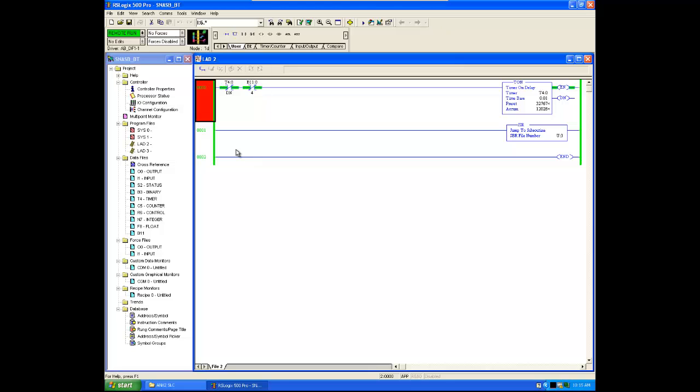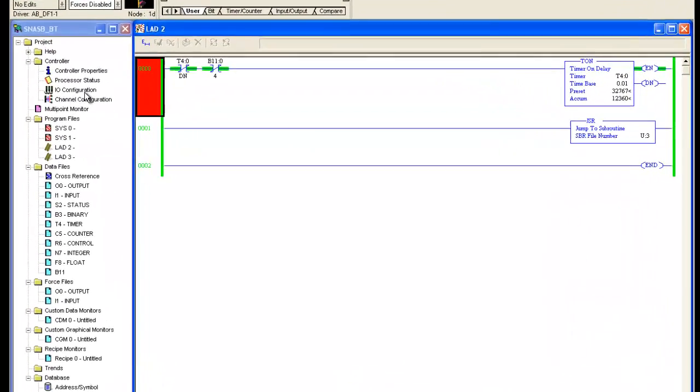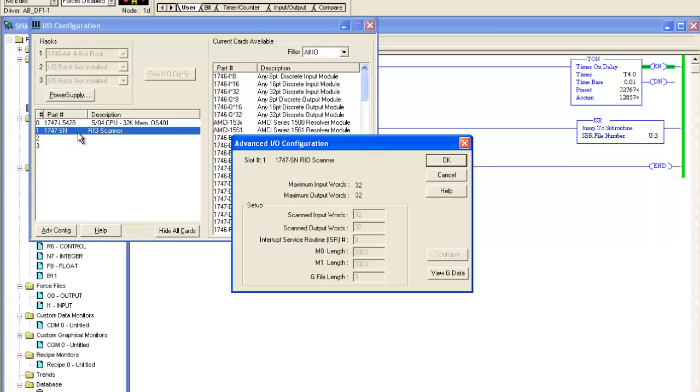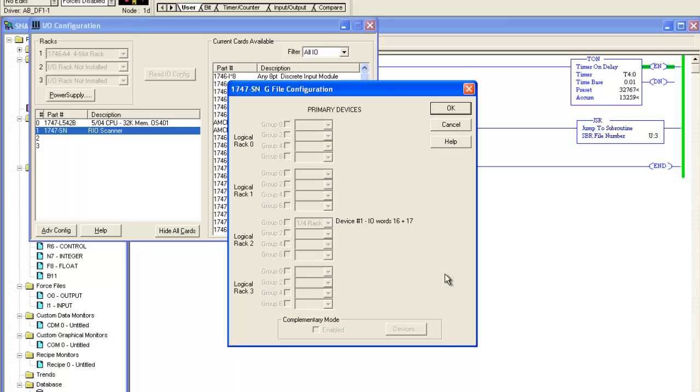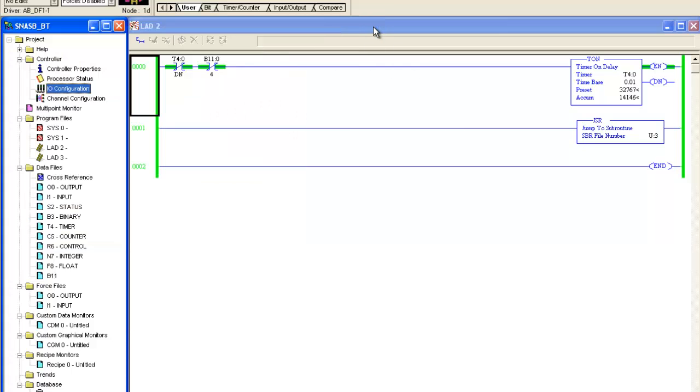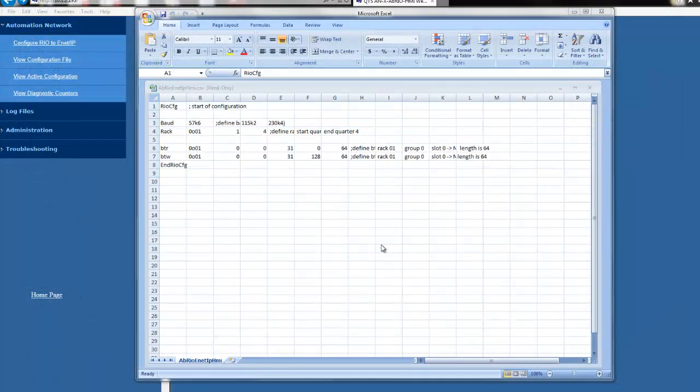We'll open up RSLogix 500 and take a look at the current RIO scanner project so that we can emulate the settings. The SLC is using a 1747 SN Remote I.O. scanner to communicate to the old HMI. Before we can program the Annex module, we need to look at a couple of settings in the program. First, we'll look at the G data in the Remote I.O. scanner card. This will tell us the rack, group, and length that the existing HMI was using to communicate to the I.O. files in the processor. This scanner card is set up at Rack 2, Group 0, for a quarter rack.